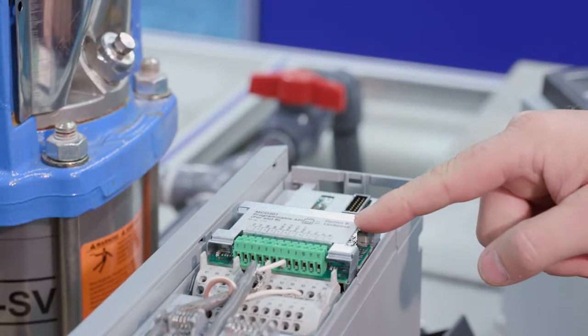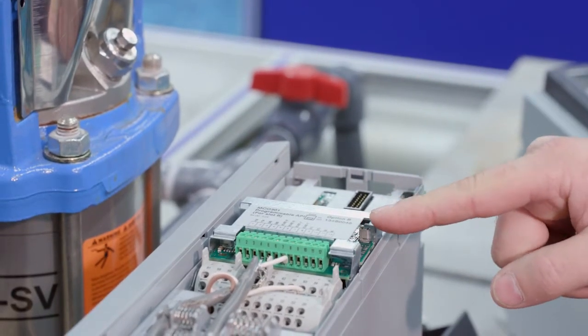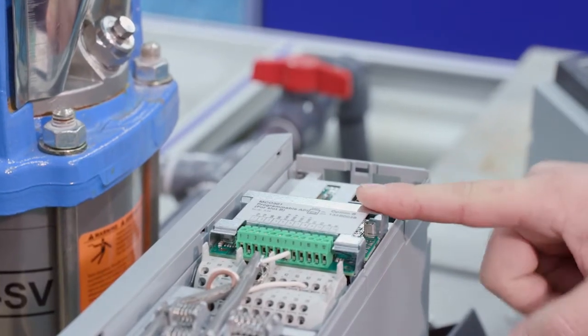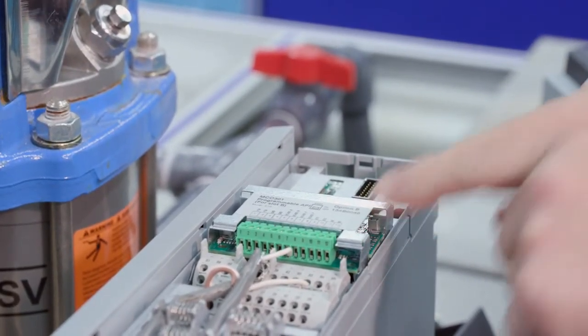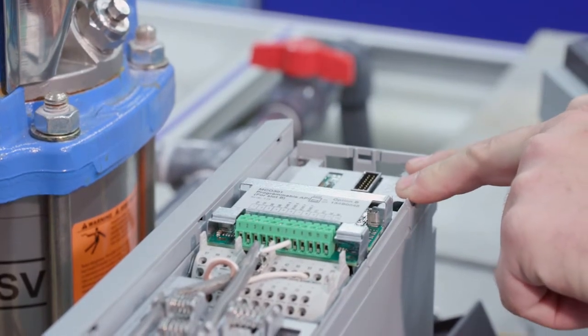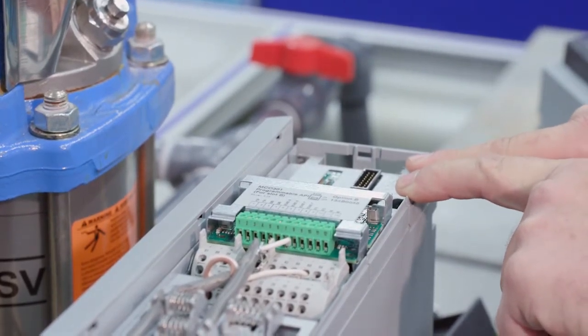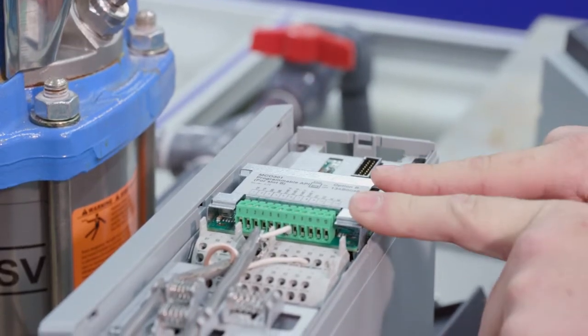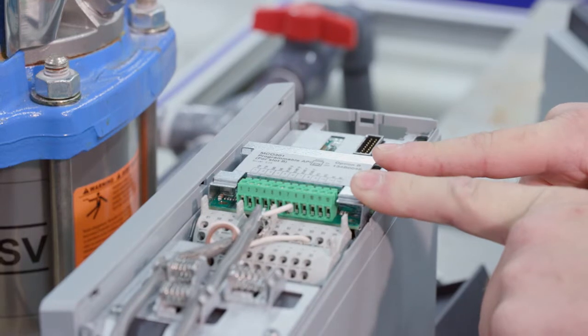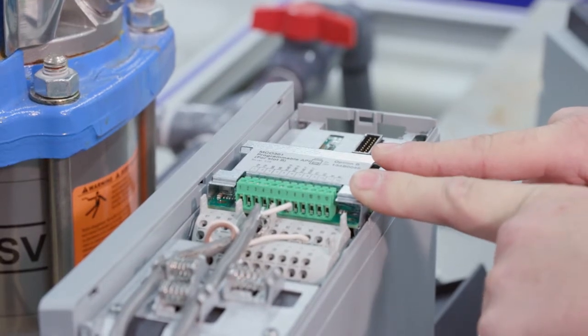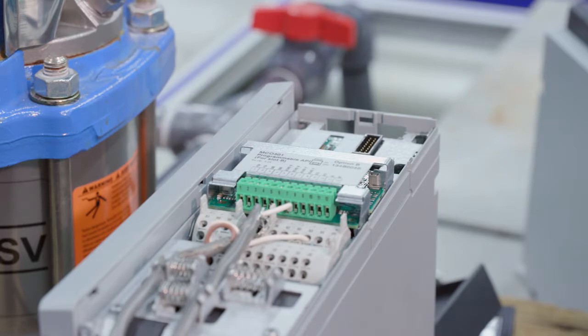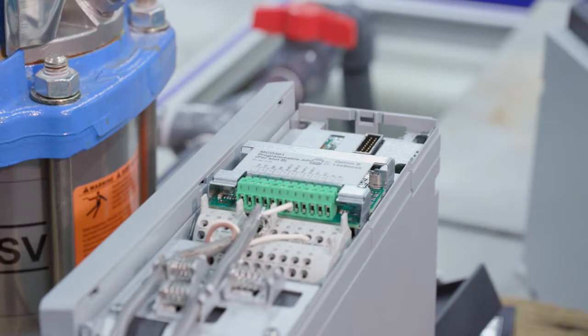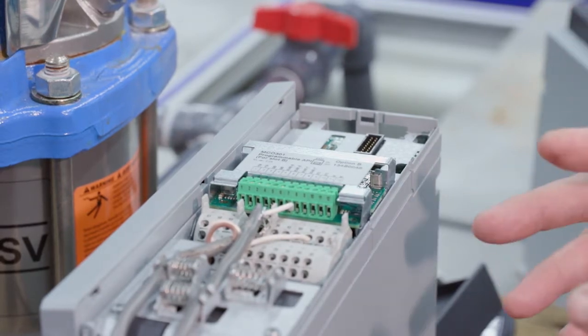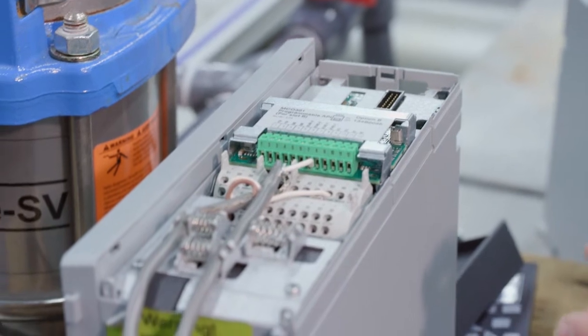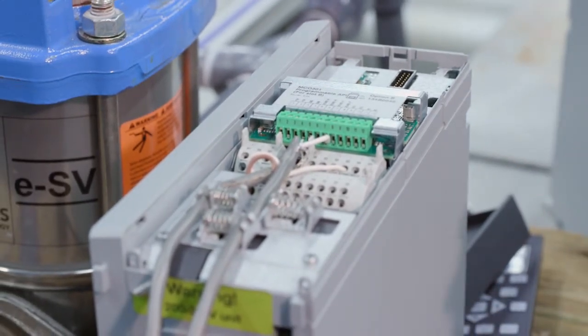So this is the MCO 301 card that is standard. We can see here option B, and that's what's called the B slot. And the optional card would be on the A slot. So one feature that is very beneficial with the new card is additional multi-pump features. One is synchronous and the other is a true multi-master, multi-control, and much easier wiring. This will allow us to operate up to 4 pumps in multi-control.